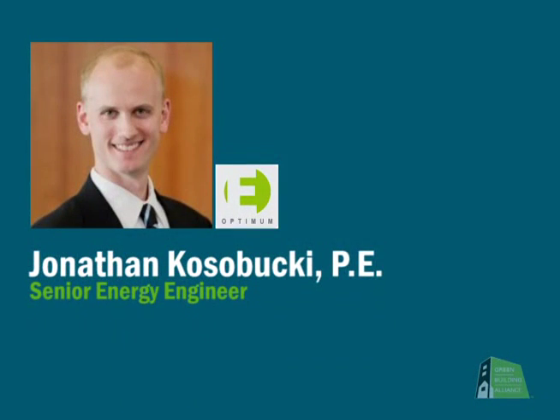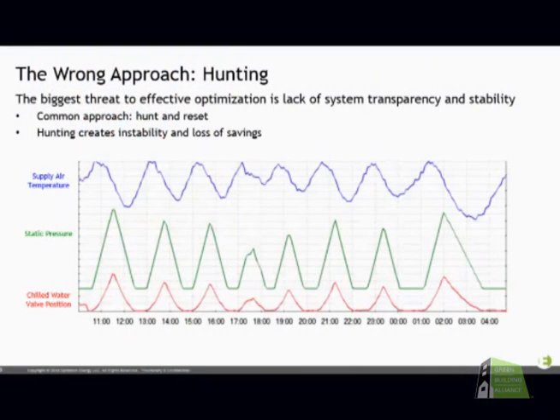Great. So what we're showing here is basically a more traditional style of controlling an HVAC system. This graph on top shows supply air temperature into a space. So in this room we have a duct right up overhead. Whatever the temperature in that duct is, you're going to measure. And at the very beginning of this graph, we're satisfying all set points. We have the right supply air temperature, enough static pressure and chill water at the temperatures we want. Now, as whatever load is happening on a building, when it starts to warm up, be that from people, computers, solar load, you're going to have that temperature rise a little bit.